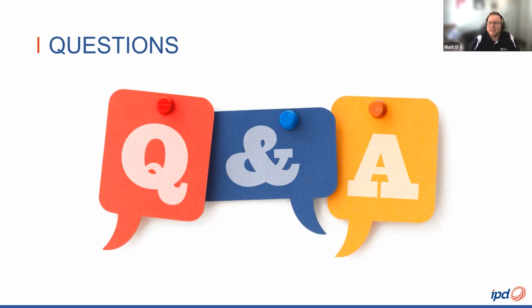A couple of questions here, pretty much in that same vein, that I'm going to tick off with. There was one question here regarding whether a type AC can still be used to replace a type AC. We just covered that one. That was part of the advice MEA sent out at the start of the week with regards to the new ERAC notice. So same again, if you are replacing a type AC that is damaged, you can put another type AC in. This is generally more used in situations where we have existing chassis style switchboards of which the manufacturer does not have a specific type A available for replacement and refitment. But we'd always recommend, where possible, to upgrade to those type As.